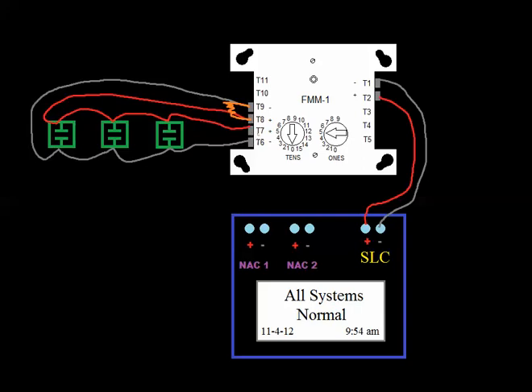So this terminal 6 and 7, it still sees a resistor, but here's the advantage. Basically, in a class A circuit, you would have, this module would be putting out its power on both terminals 6 and 7 and on 8 and 9. So if I were to come in and cut just one wire, let's say I cut the wire right here.